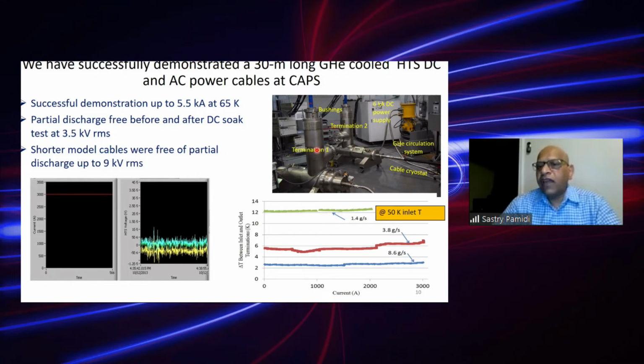The primary variable we have in cooling a device with helium gas is the flow rate, the mass flow rate. And mass flow rates and the operating temperature and temperature gradient are related. As you can see here, current is on the x-axis, and this is delta T, meaning the temperature gradient between the inlet and the outlet. So how much the temperature of the gas increases when it cools a 30-meter long cable. If I use a small flow rate, or 1.4 grams, you can see the delta T is 12 Kelvin. So the inlet gas is at 50 Kelvin, the outlet gas will be at 62 Kelvin.